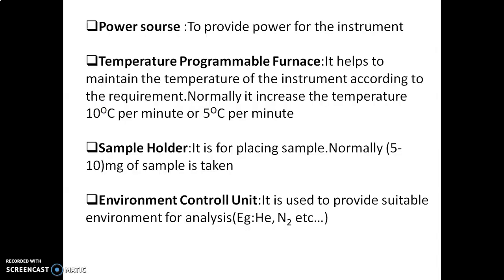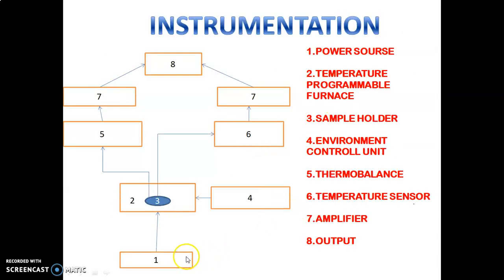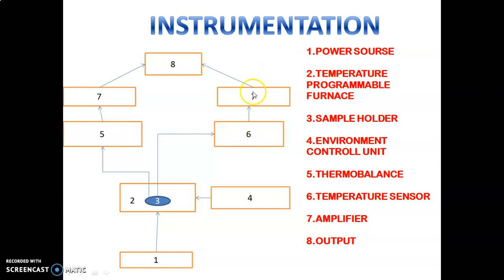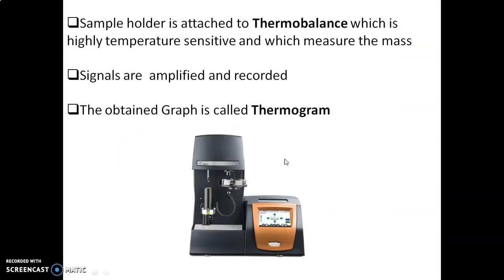To summarize the instrument flow: we provide power to the temperature programmable furnace; the sample is placed according to the program; the environment controller unit provides the required atmosphere; the thermobalance measures mass; the temperature sensor records temperature; the two data signals go to the amplifier; and the output is known as the thermogram.